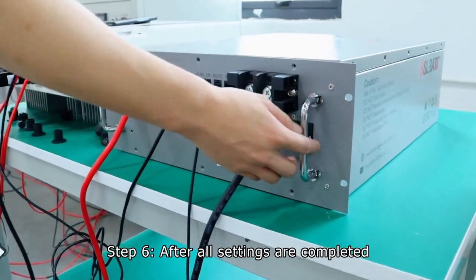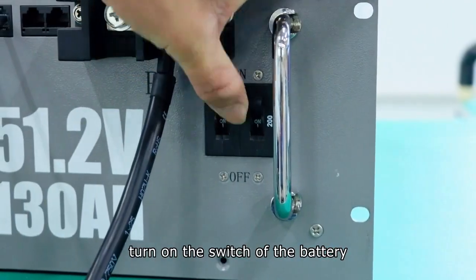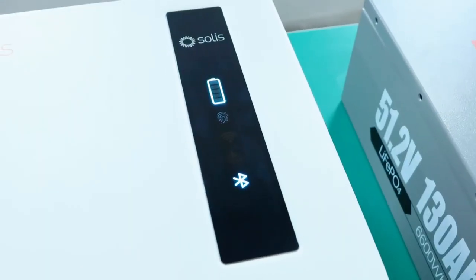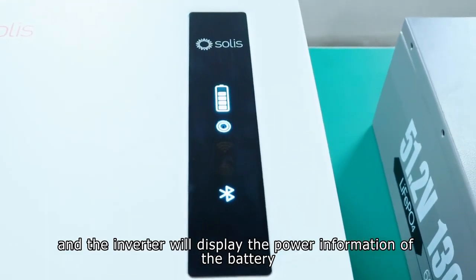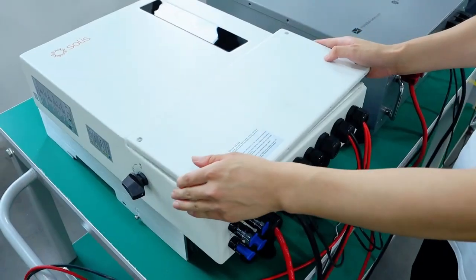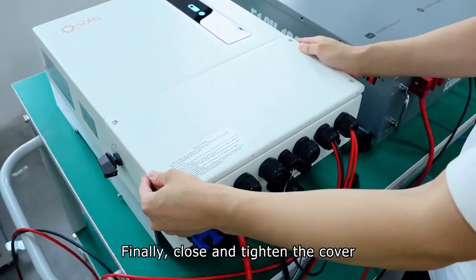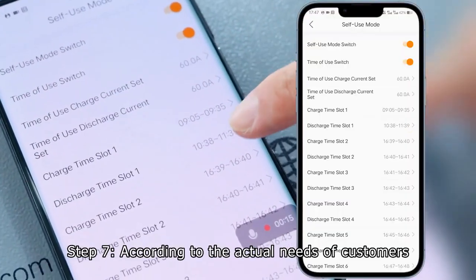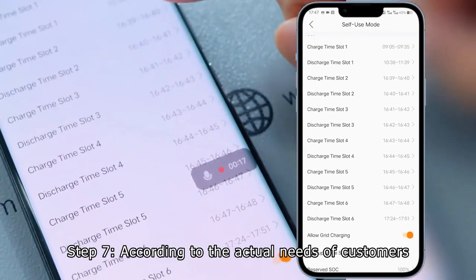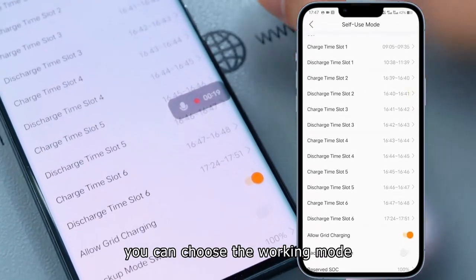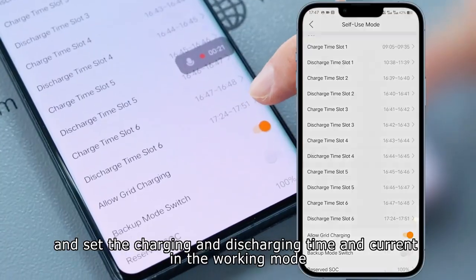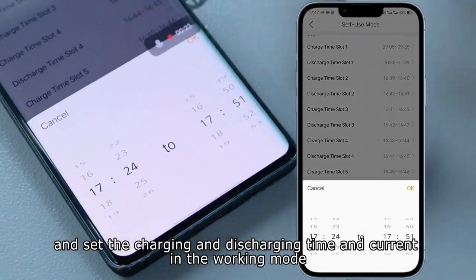Step 6. After all settings are completed, turn on the switch of the battery. And the inverter will display the power information of the battery. Finally, close and tighten the cover. Step 7. According to the actual needs of customers, you can choose the working mode, and set the charging and discharging time and current in the working mode.